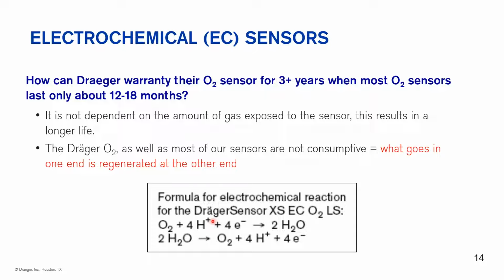So how can we get away with warranting our oxygen sensor for so long when most other sensors out there don't? Well, again, it's not dependent on the amount of gas our sensor sees. Other sensors on the market may have a lead base electrode, and that lead base electrode actually deteriorates as the sensor reacts to the oxygen. So once that lead electrode basically gets consumed, that sensor will stop working. It can work today, not tomorrow. It can die that fast. And we don't have a lead-based electrode in our sensors.